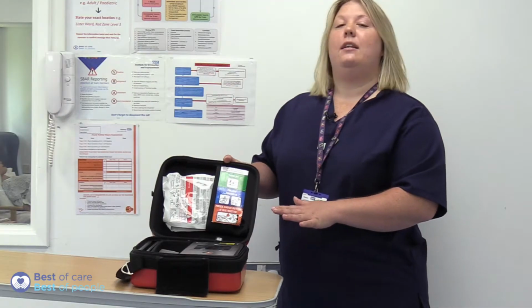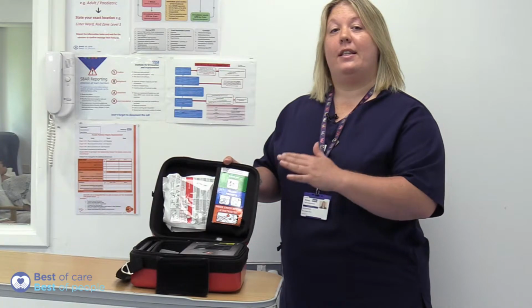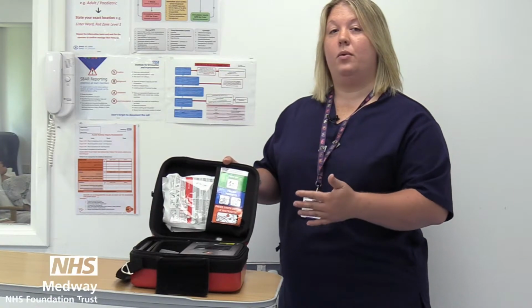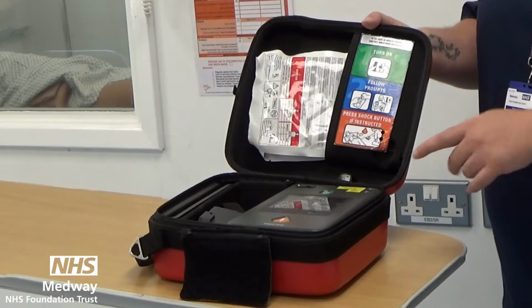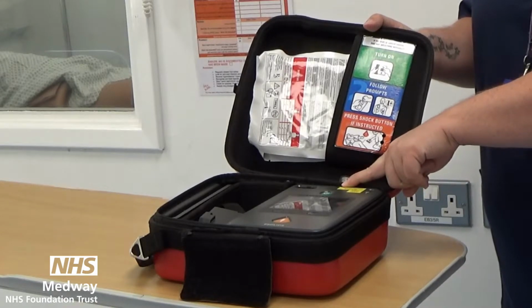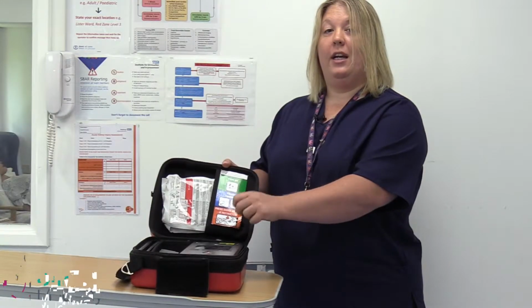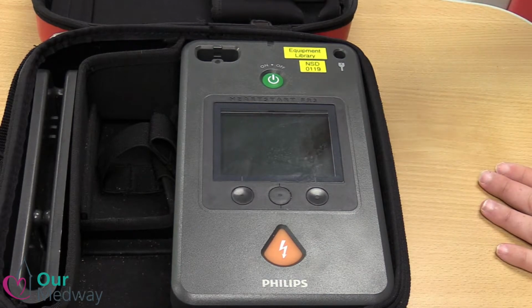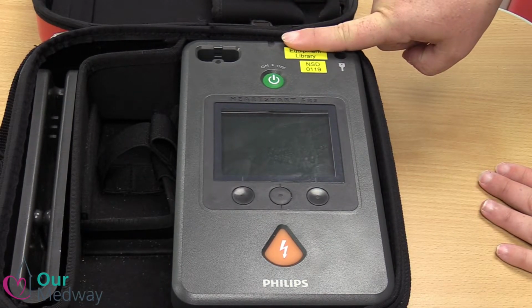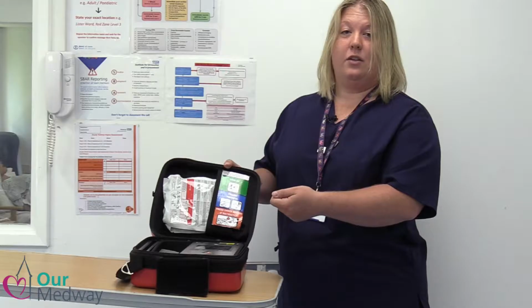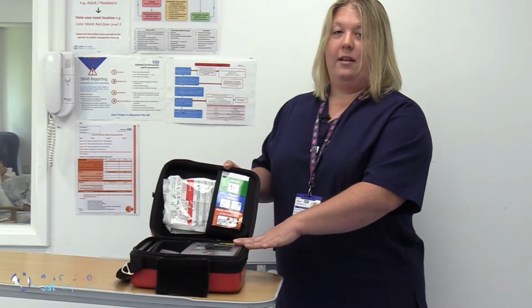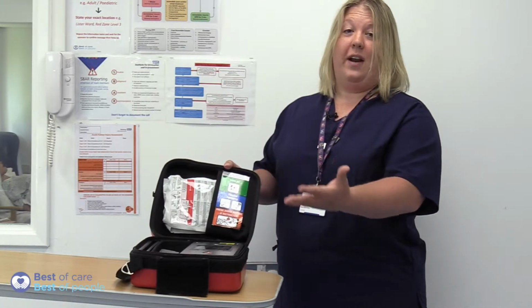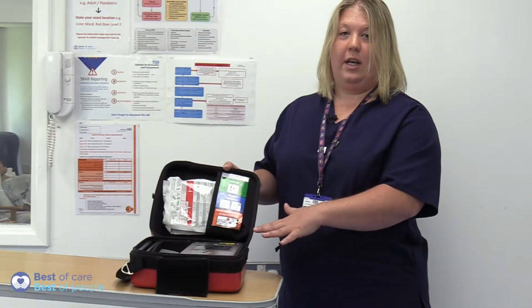These defibrillators need to be checked every day. They are self-testing, so it's a really simple check that we need to do every morning, and it's simply that the green light at the top is flashing continuously. You can see that this one is not, and you can hear that it's beeping regularly as well. So this indicates to me that this battery is flat or that there's an issue with this defibrillator.